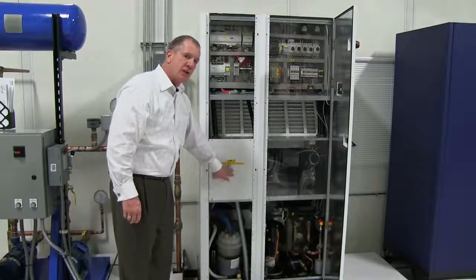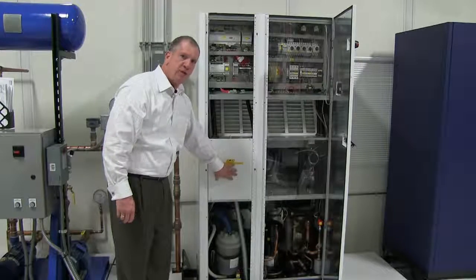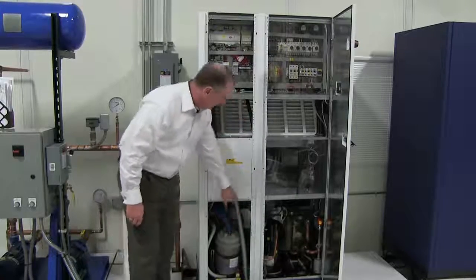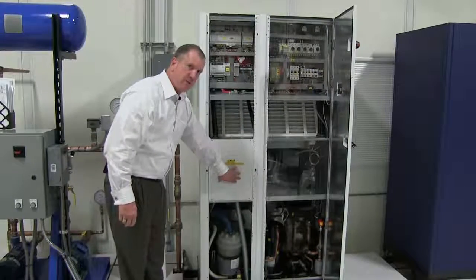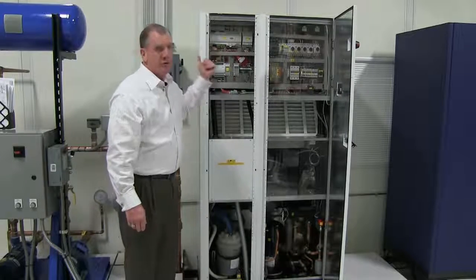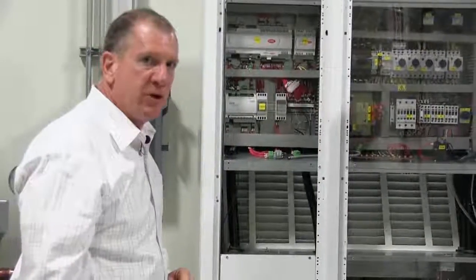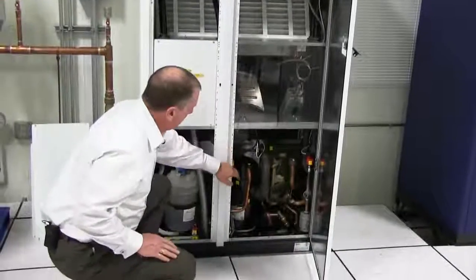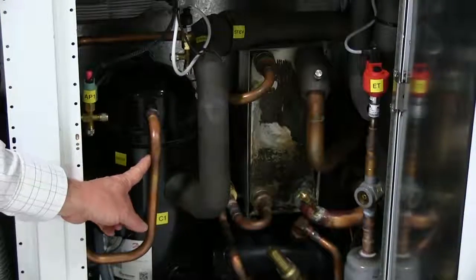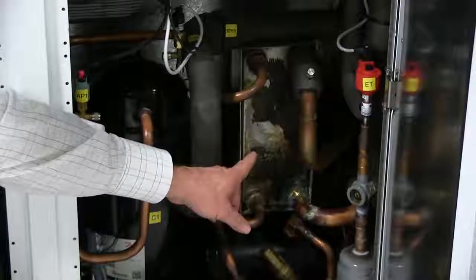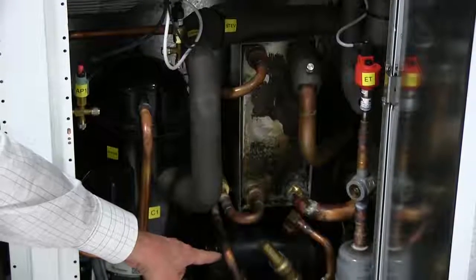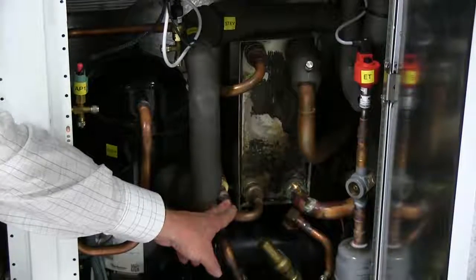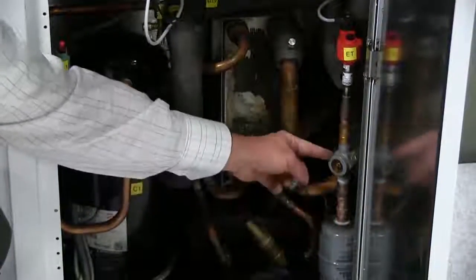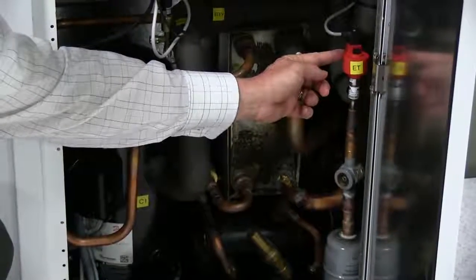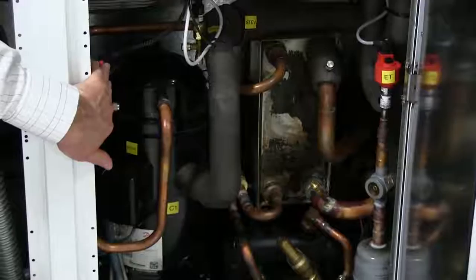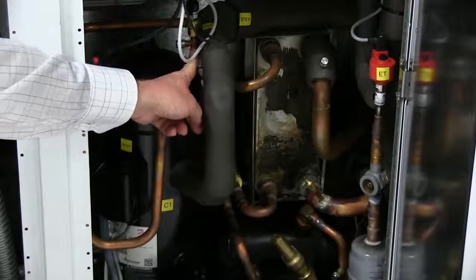Behind this internal panel is an additional electrical box allowing single point power connection to the power feed to the unit. The electrical contractor would bring his conduit in and connect to the single point power terminal strip. The remainder of the unit is wired internally to the electrical panel. Now moving down to the machinery compartment, we have a highly efficient scroll compressor, a 304 stainless steel brazed plate heat exchanger, the receiver, the head pressure control valve for the flooded receiver, filter dryer, sight glass, and electronic expansion valve. We also have a high pressure switch with manual reset and a low pressure switch for loss of refrigerant.